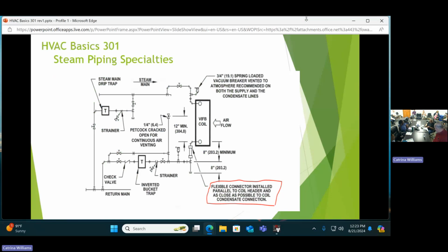Are these the same system they use in Europe, like radiators in every room to heat and cool? Yeah, that same flow that we were showing could be a branch going off to heat radiators or fin tube baseboard. I noticed they have it in the floor too. Yeah, in-floor heating, and the same way with the snow melt system. They melt snow off driveways with radiant flooring.